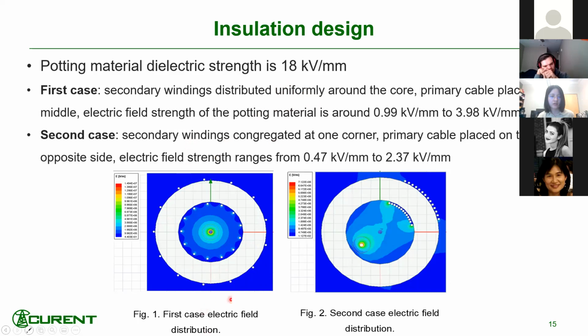And here shows 2 cases. The first case is where the windings are distributed uniformly around the cores, and the cable is placed exactly in the middle. And as you can see here, the field strength ranges from 0.99 to 3.98. And the second case is I try to separate the primary cable and secondary windings further apart. And so you can see here, this electric field is not uniform, and it would further reduce the maximum electric field that this material would experience.